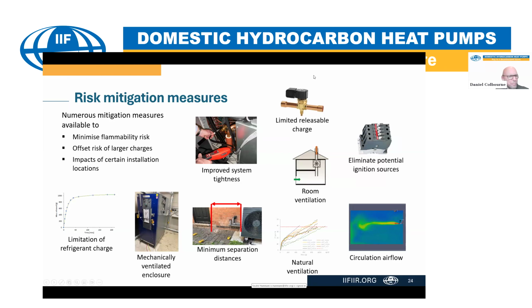Not all of them are mentioned here, and they're distributed across different standards, but just to mention a few, there is of course improved system tightness, which most of you would agree is of importance. There's what we call limited releasable charge, where you can use valves or other components to prevent a proportion of the refrigerant from leaking out of the system in the event of a leak. You can apply room ventilation to extract a release of refrigerant and eliminate potential ignition sources. That's generally applicable to all cases. And there is the circulation airflow option, which enables a release to be dispersed almost homogeneously throughout the room.